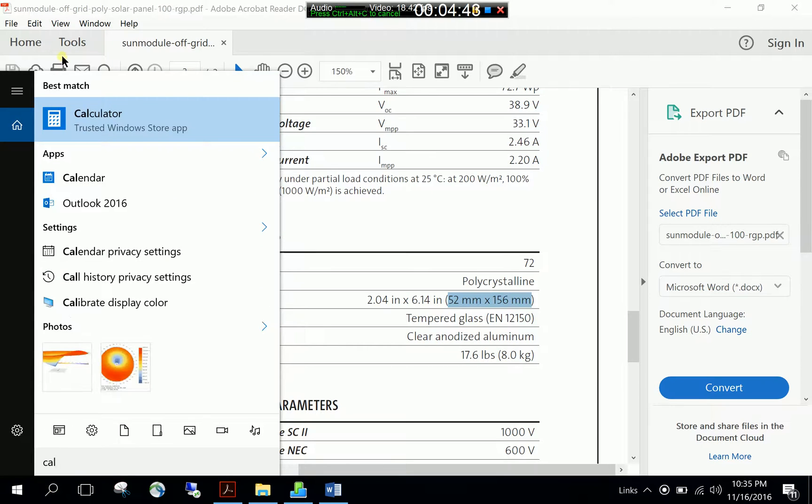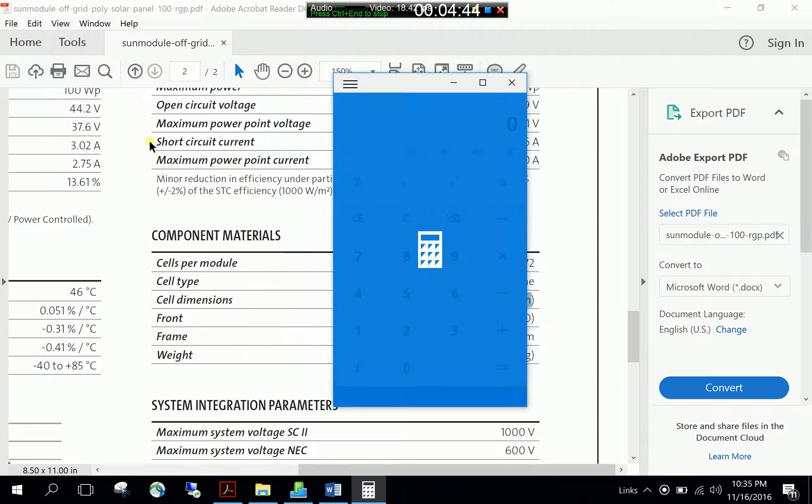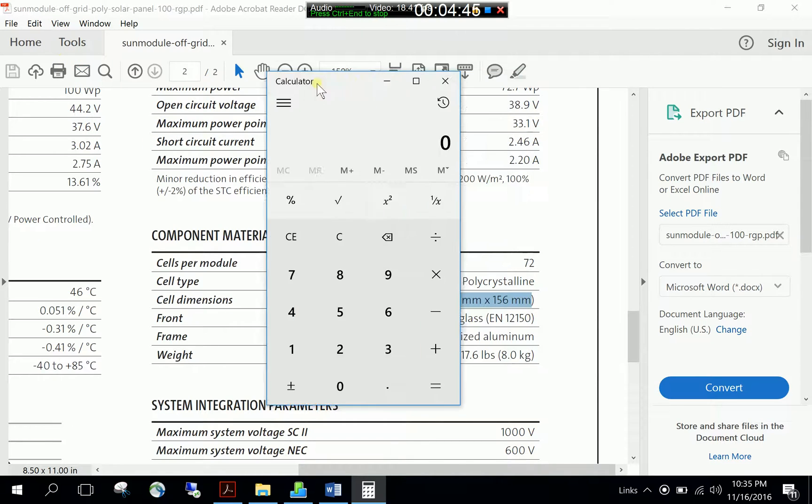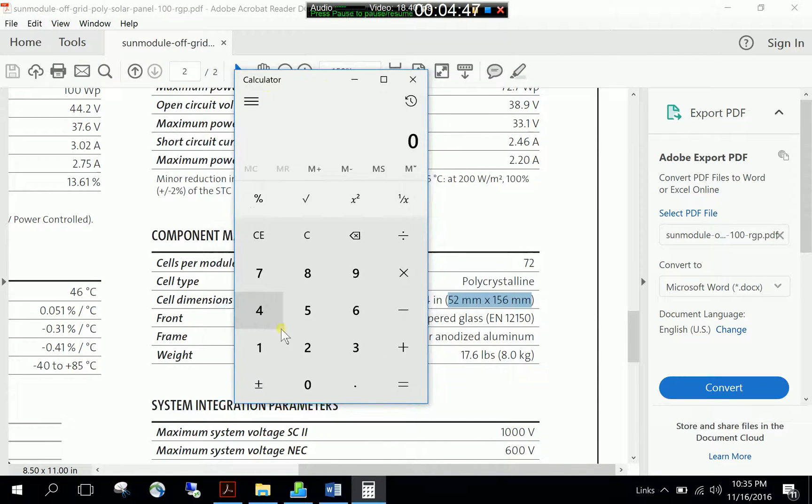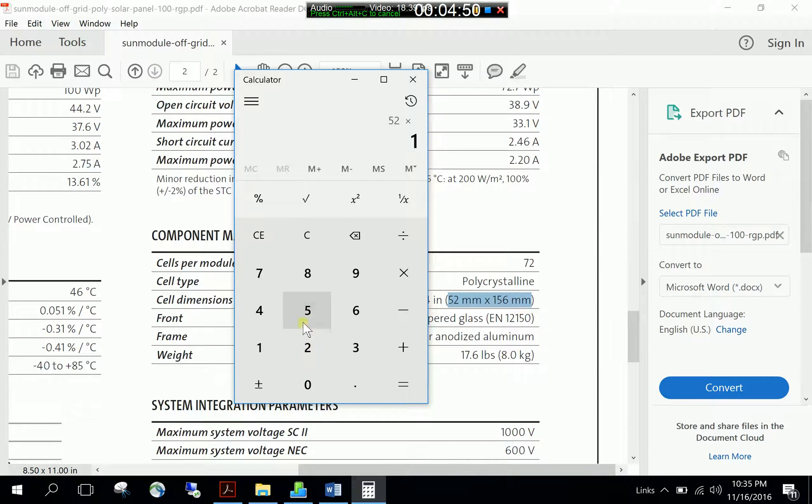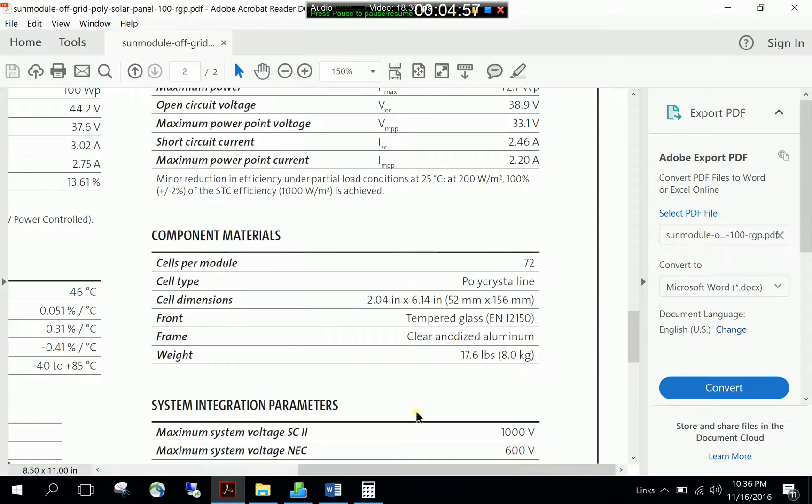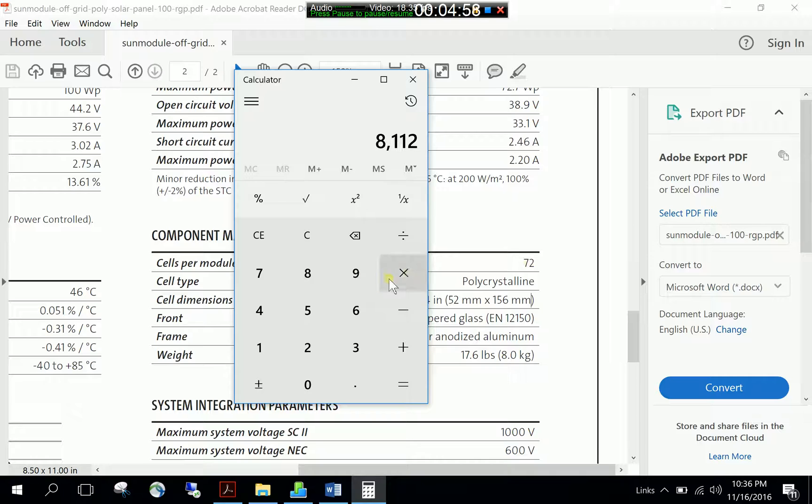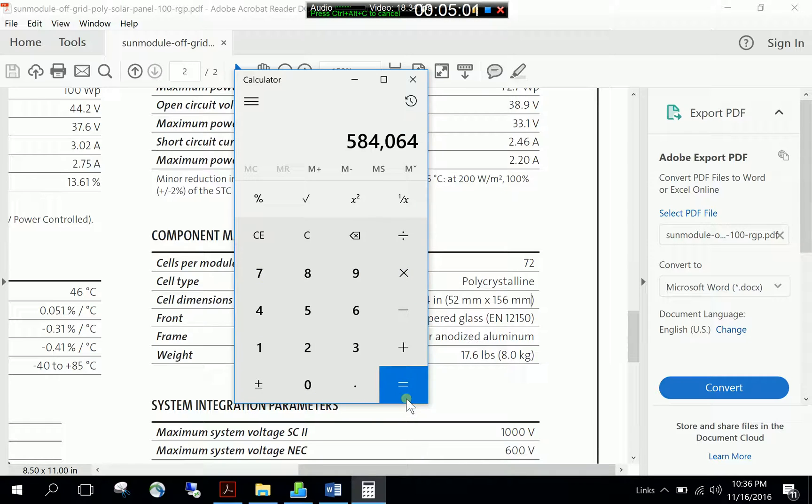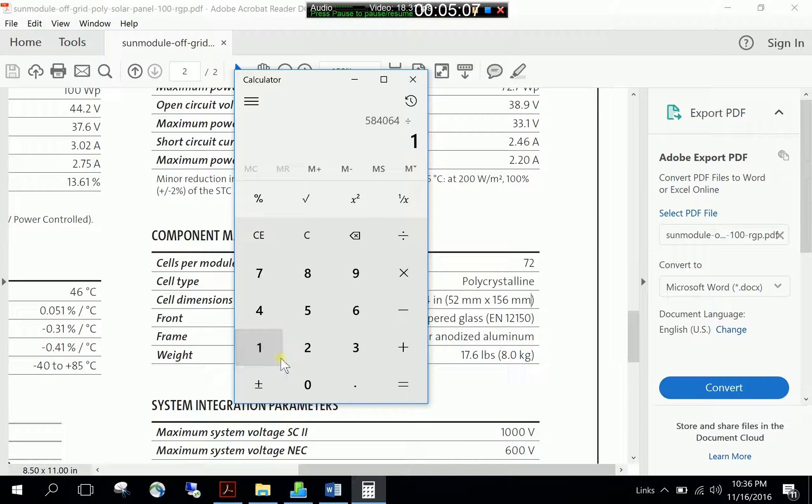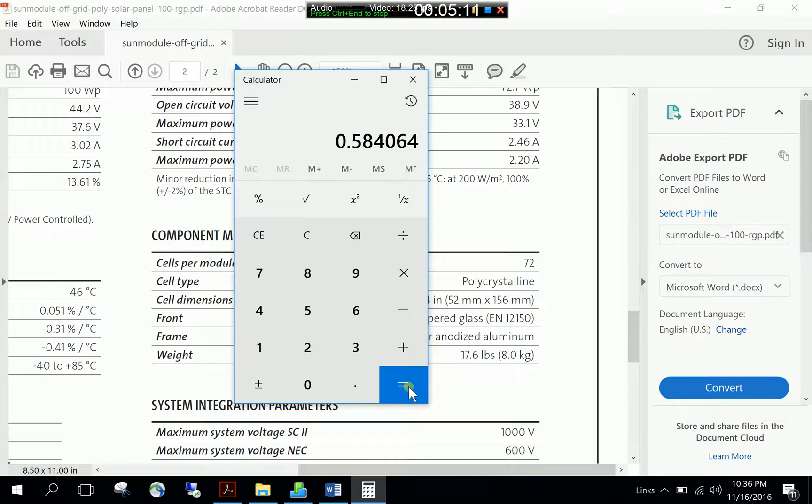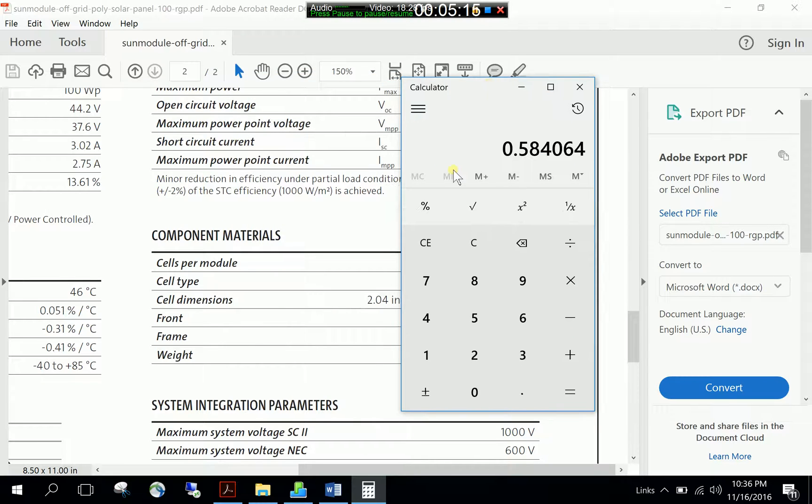Here I see that each cell is about 52 millimeters by 156 millimeters. Solar cells are normally found in rectangular or square shapes. Here I have a rectangular shape. So moving onwards, I can open up the calculator and just calculate the area of this solar cell. And then times 72, because I have 72 solar cells in this module. I can calculate the entire active area. But remember, this is millimeter square. So I should convert it to meter square by dividing by 1 million and this is my area. It's about 0.58 meters square.